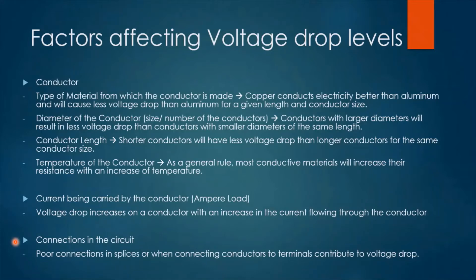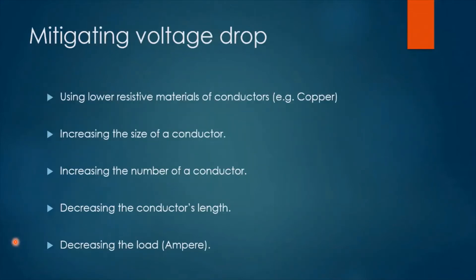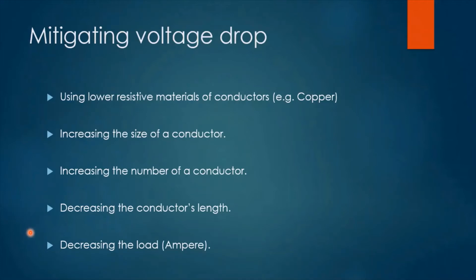Connections in a circuit may also have an effect on the voltage drop level. Poor connections, especially when connecting conductors to terminals, contribute to increasing the amount of voltage drop. To mitigate or decrease voltage drop in a system, we can apply different techniques: using lower resistive materials like copper instead of aluminium, increasing the size of a conductor, increasing the number of conductors, decreasing the conductor's length, and by reducing the load or current passing through a conductor.